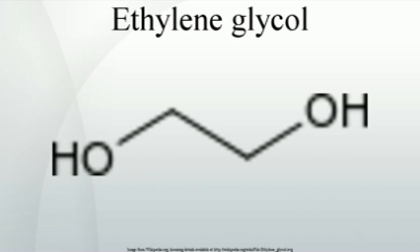Additionally, the increase in boiling point over pure water inhibits nucleate boiling on heat transfer surfaces, thus reducing heat transfer efficiency in some cases, such as gasoline engine cylinder walls. Therefore, pure ethylene glycol should not be used as an engine coolant in most cases.